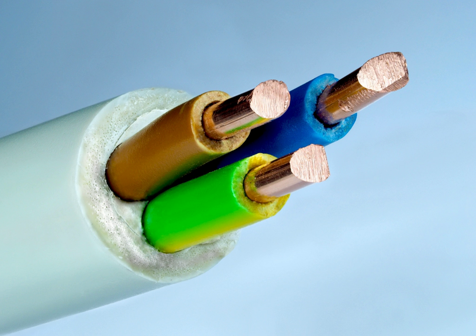Shielding makes use of the electrical principle of the Faraday cage. The cable is encased for its entire length in foil or wire mesh. All wires running inside this shielding layer will be to a large extent decoupled from external electrical fields, particularly if the shield is connected to a point of constant voltage, such as earth or ground.